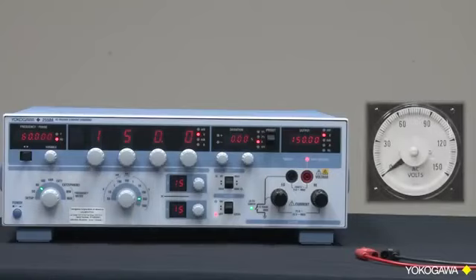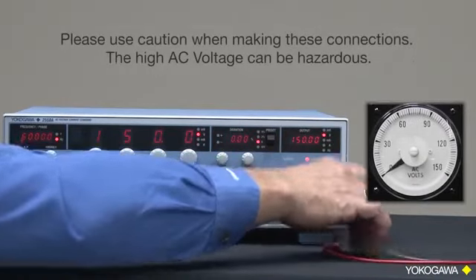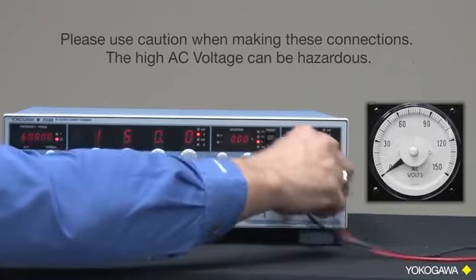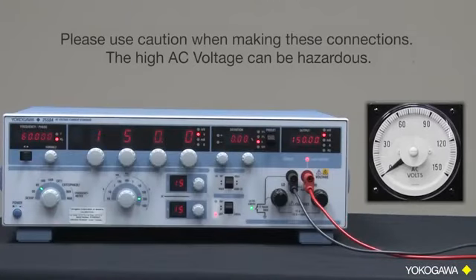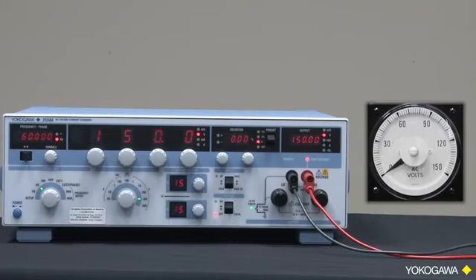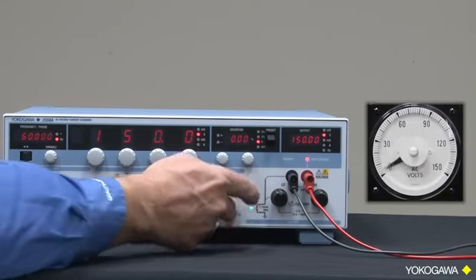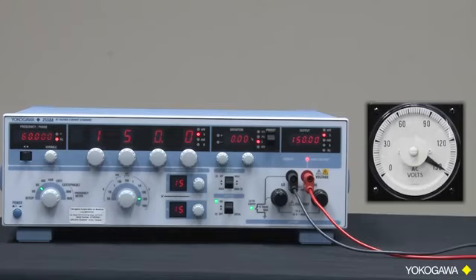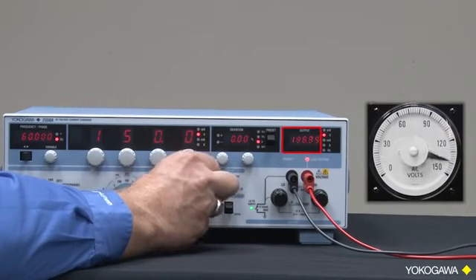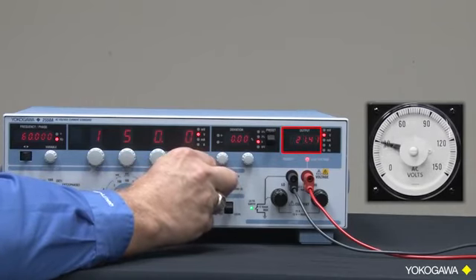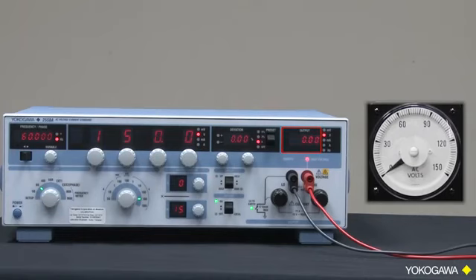I will now connect the panel meter under test to the source. Next, I will turn on the output to the source. Using the output divider knob, I will now step the voltage down one step at a time. Each click will decrease the reading on the panel meter one major division. At any of these points, the accuracy on the panel meter can be checked. The specified accuracy of this panel meter is 1% of full scale.